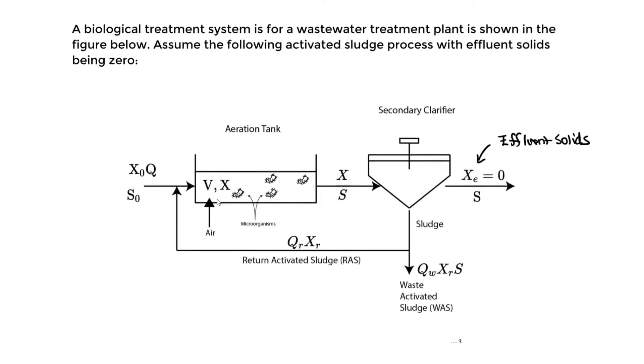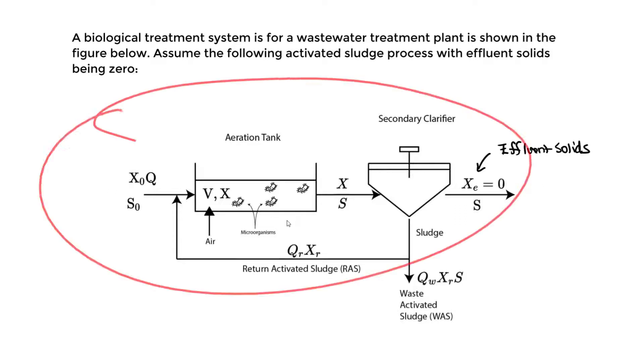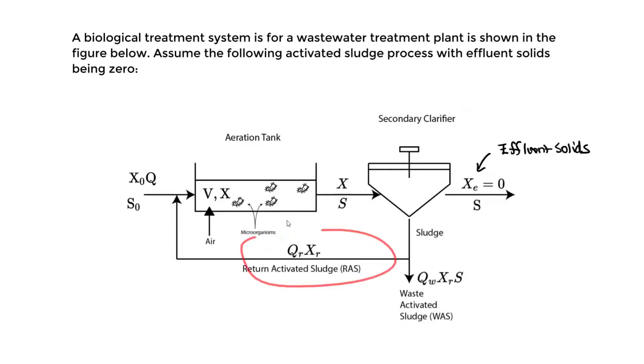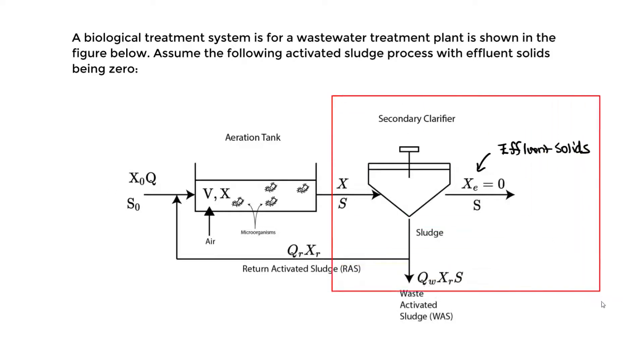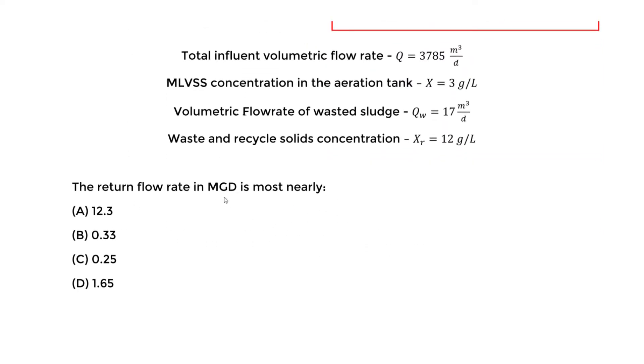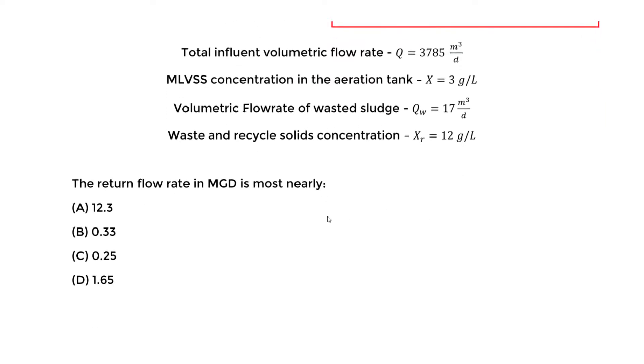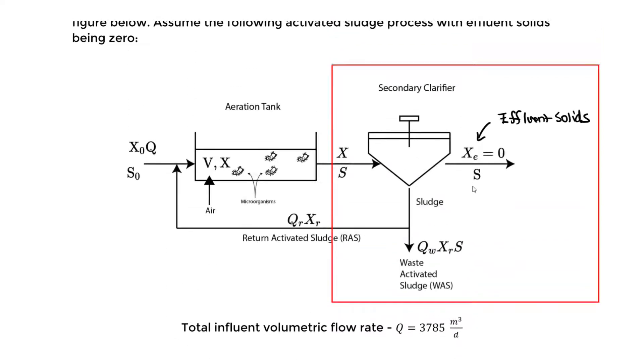To solve this, I propose doing a mass balance. We need to decide which system to isolate. We could do the overall system, but since we're looking at the return activated sludge, which is mainly concerned with the secondary clarifier, we're going to isolate just the secondary clarifier and apply a mass balance to it, with the end goal of finding Q sub R, the recycle flow rate.